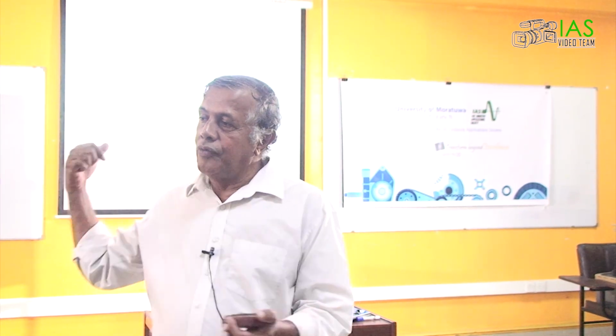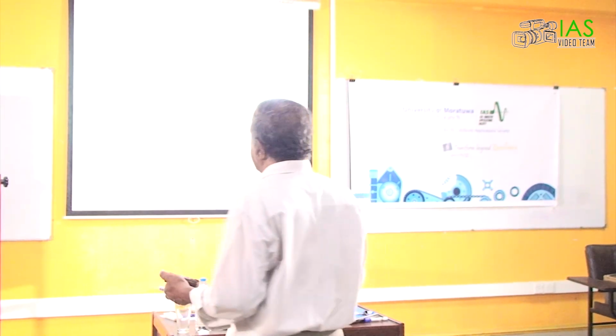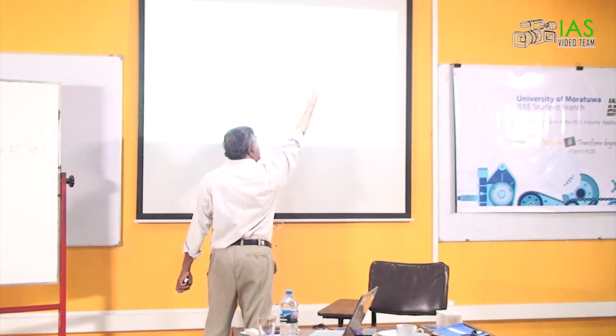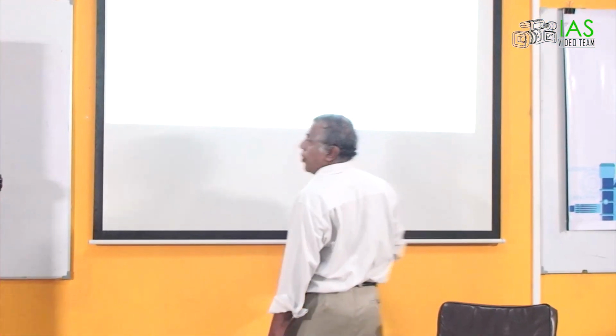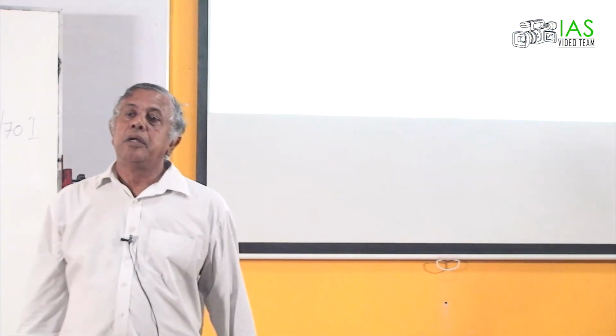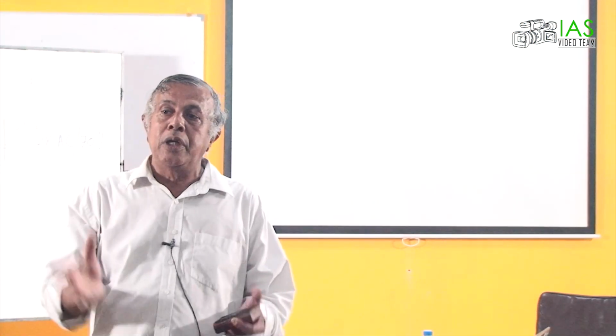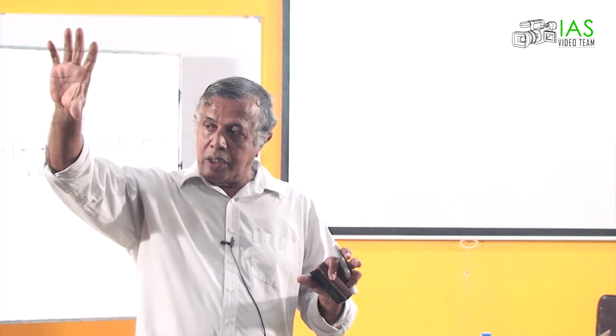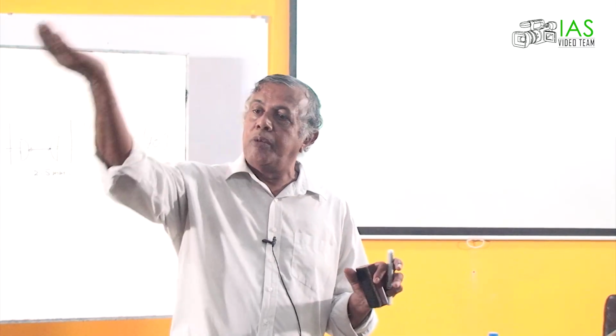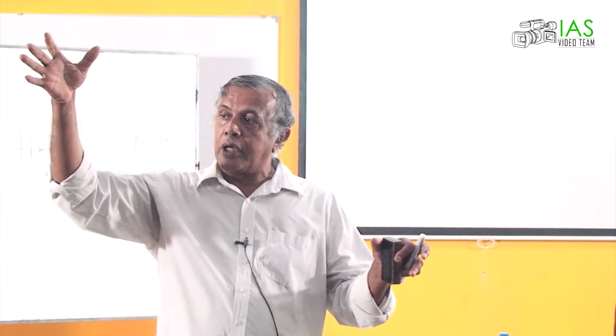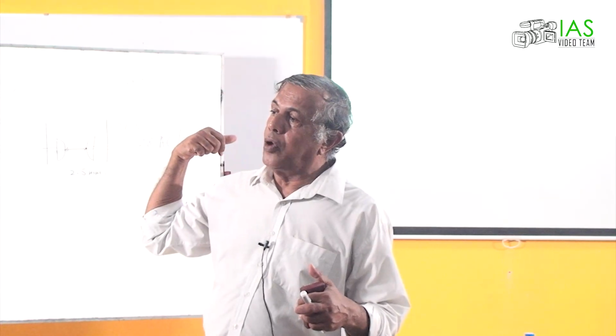What happens? If the restricted earth fault is not there, it wouldn't detect because the CTs are there. Now, these CTs would detect the faults onto other side, not within. Now, this is a zonal protection between the phase current transformers and the neutral transformer. So, that zone is protected by restricted earth fault.